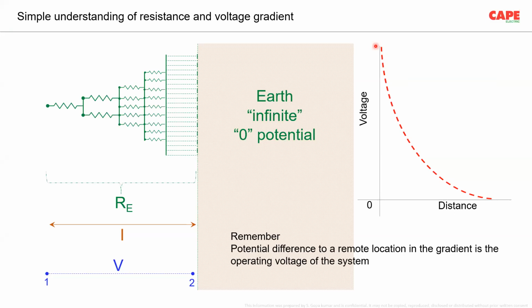But practically what happens is, most of these inquiries are coming for applications like low voltage, 230 volt. Actually, in 230 volt, I would say, of course, there is a voltage gradient, but within half a foot the majority of the voltage is over. The shock is over. So basically, in 230 volt, this is, I would say, not very important. Instead, you make protective equipotential bonding.